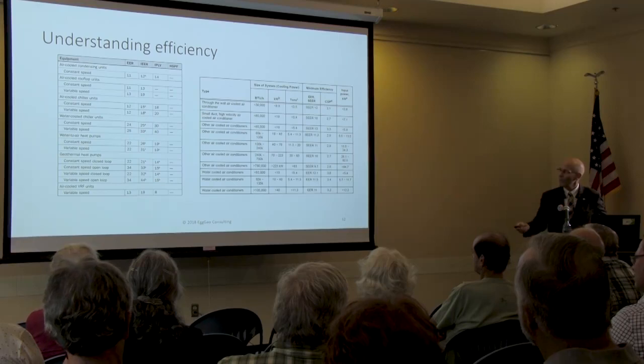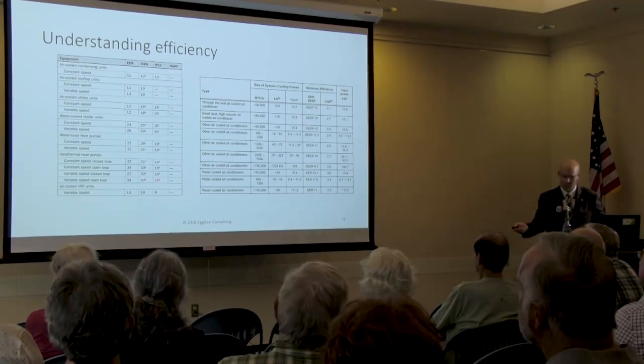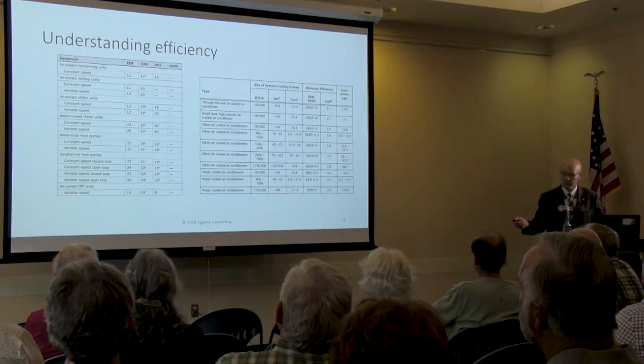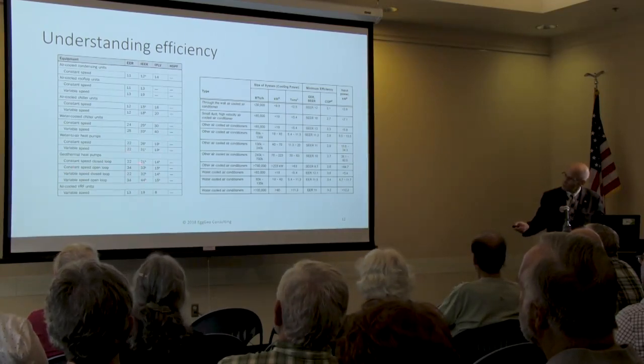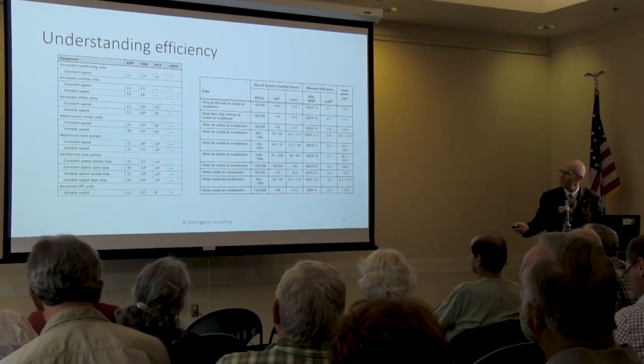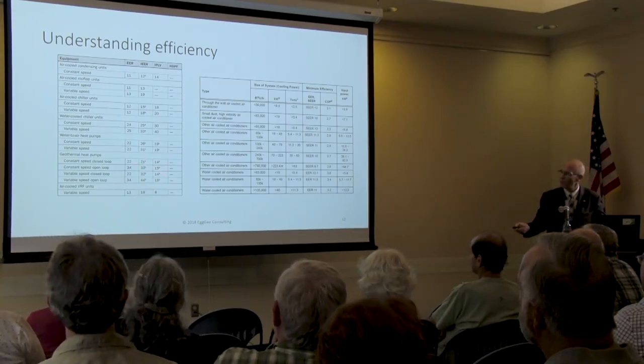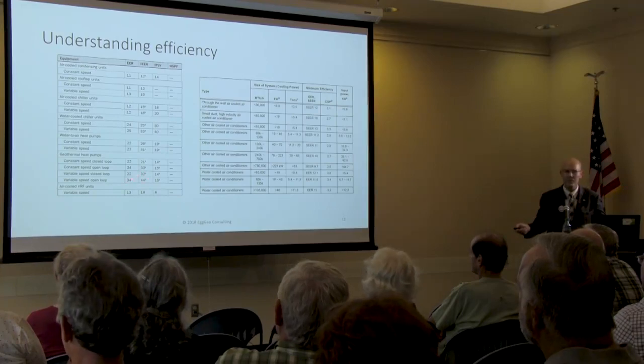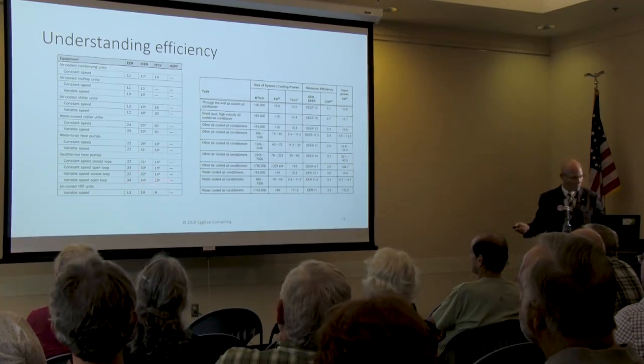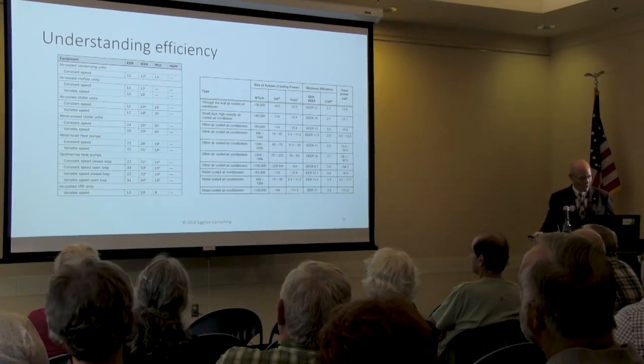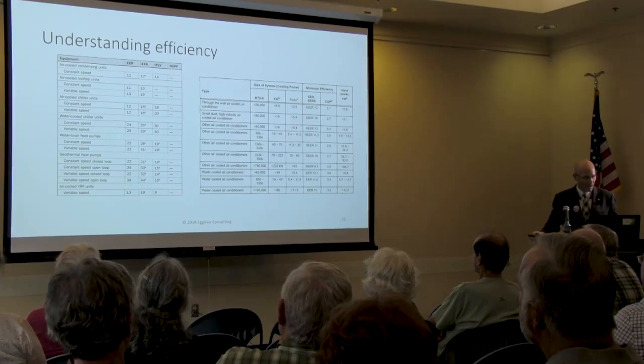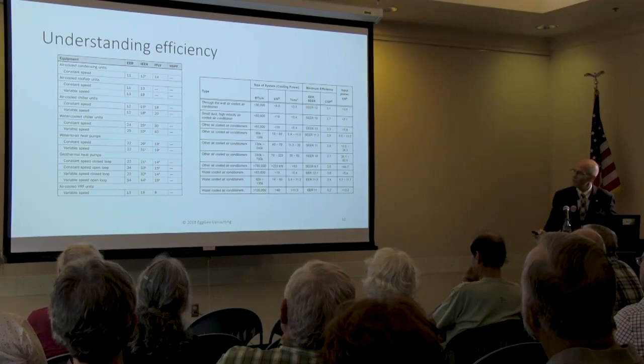This chart over here has a little bit more about the efficiency of air-cooled versus geothermal when you start looking at your geothermal heat pumps. And unfortunately, people in the U.S. still love to rate them in EER, so it's a necessary evil, but look at how efficient some of them get. 44, 32, 33 integrated EER, 34, 22 for the steady state EER, compared to the air source constant speed units that are about a third of that. So that's how we understand a little bit about the efficiency of geothermal air conditioning and heating systems in general.